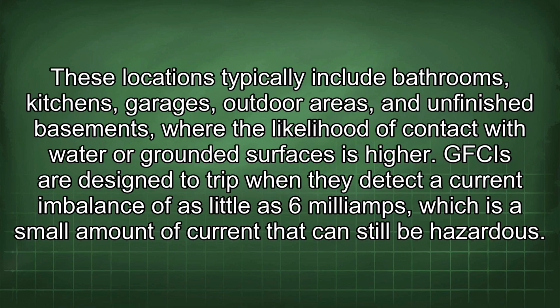These locations typically include bathrooms, kitchens, garages, outdoor areas, and unfinished basements, where the likelihood of contact with water or grounded surfaces is higher. GFCIs are designed to trip when they detect a current imbalance of as little as 6 mA, which is a small amount of current that can still be hazardous.